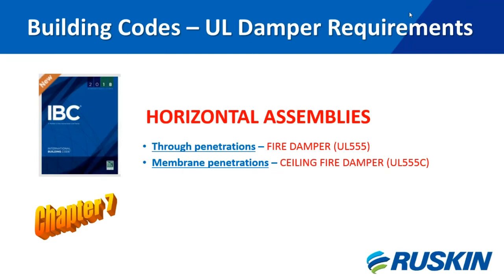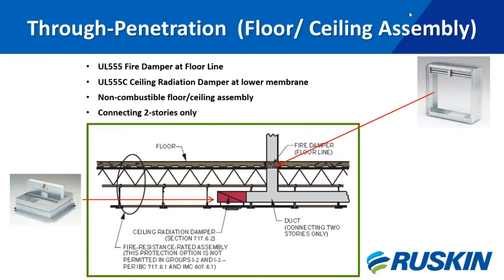For building codes regarding horizontal assemblies, this is where many people get confused about what type of damper can be used. For through-penetrations, depending upon the occupancy type and how many stories the building is, you may only need a fire damper in the assembly, or you may need to build a fire-rated shaft. If the shaft wall is penetrated, then the shaft wall is to be penetrated with a fire damper and/or FSD. If there is a membrane penetration only, ceiling fire dampers and ceiling radiation dampers apply.